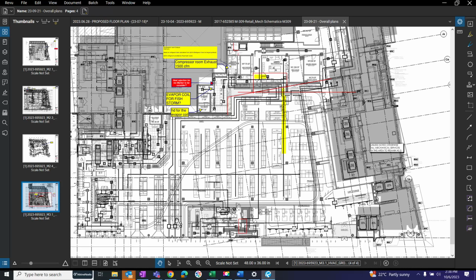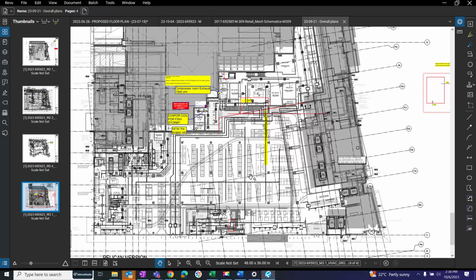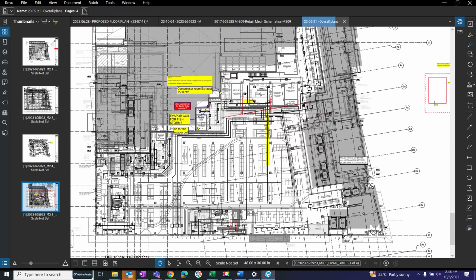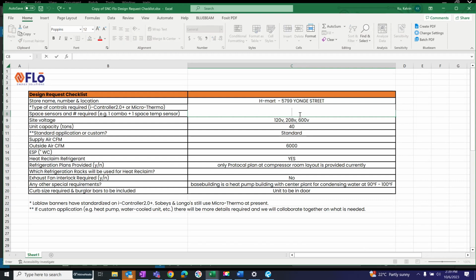I almost want to say maybe this might be a good opportunity for two sets and then take an average. What do you think, Peter? We don't want it near any airflows, airstreams, or open cases, so centrally located is usually really good. But again, maybe this one, since there's a few different zones, might benefit from two sensors and taking an average. Yeah, I mean, I can't remember all the ductwork, but obviously our unit's responsible for where the ductwork goes. Otherwise there's nothing else we can influence. So whatever gives the right reading for the area you're trying to control, that's what matters.